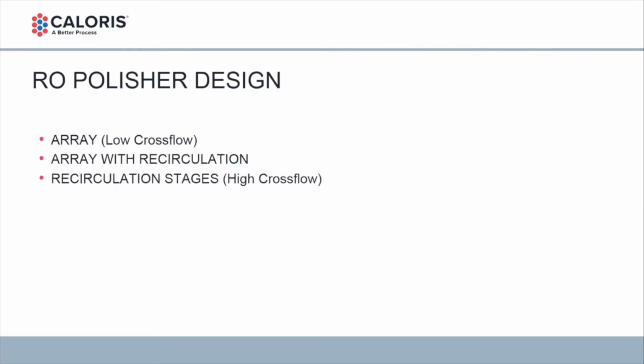Okay, RO polisher design. There are three main designs. There's the array type, that's low cross flow. There's the array with recirculation, that's going to be mid-range for cross flow. And then there are recirculation stages, which is going to be the same design as a lot of the food and dairy type plants with a lot of suspended solids, and it's going to be designed with high cross flow.